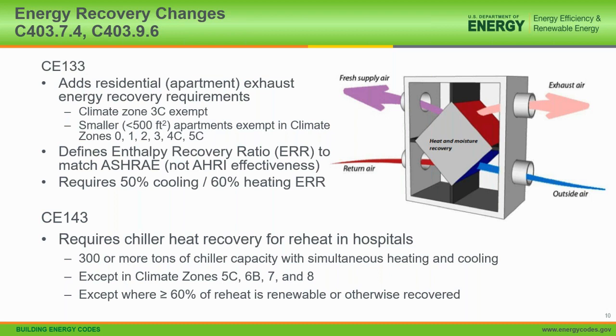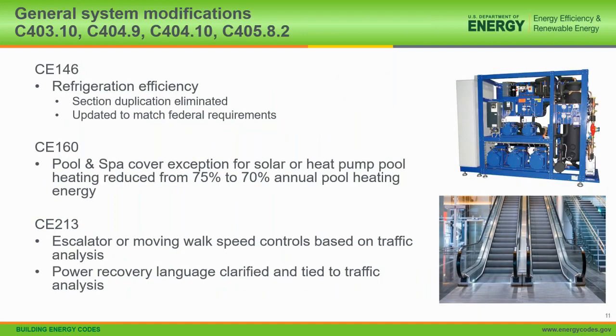CE 143 is very specifically oriented at hospitals that have VAV or constant volume reheat systems, and it says that if you've got a chiller, you're rejecting heat, so let's take that heat and put it into the reheat system. Basically, if you've got more than 300 tons of cooling capacity in the hospital in the total chiller plant, then you have to meet this requirement that says it's 7% of your total cooling capacity, so you'd have a separate smaller chiller that would provide that heat recovery and use that effectively to provide the reheat in the system. And again, that's a very specific requirement. Currently oriented to hospitals. There may be some expansion of something like that in the future, but that's what we've got now as a new energy recovery requirement.